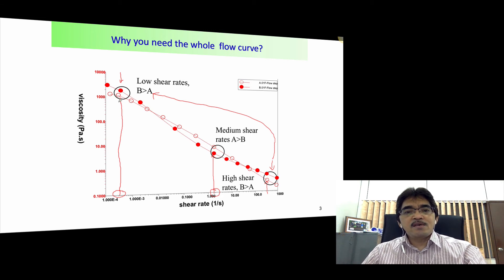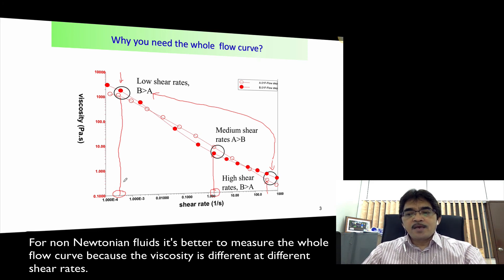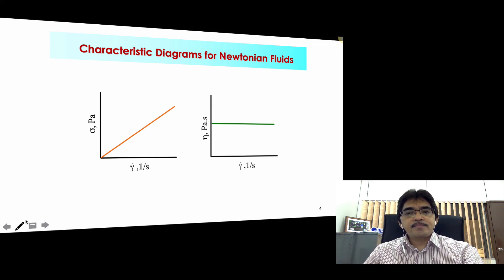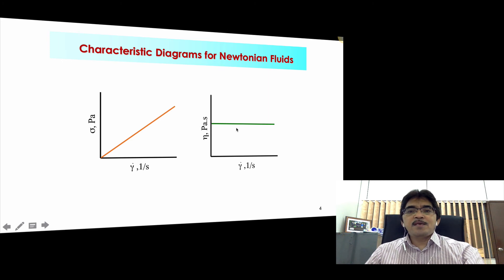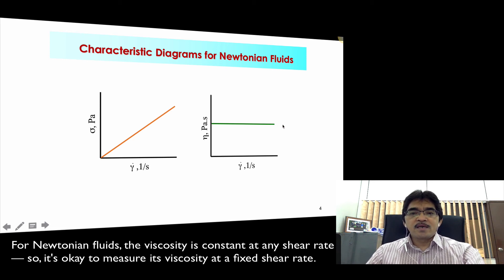It's good, in this case, to have the whole flow curve so that we can see how the viscosity changes as a function of shear rate. For a Newtonian fluid, the viscosity is constant at any shear rate. So if we plot viscosity against shear rate, the viscosity is constant. For a Newtonian fluid, we can just measure the viscosity at any shear rate because we know it will remain constant at a constant temperature.